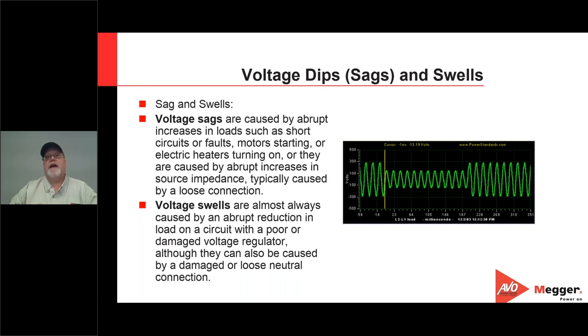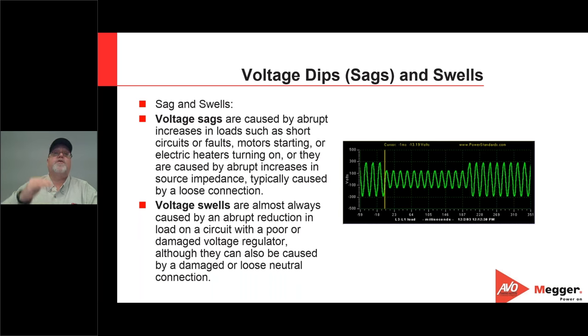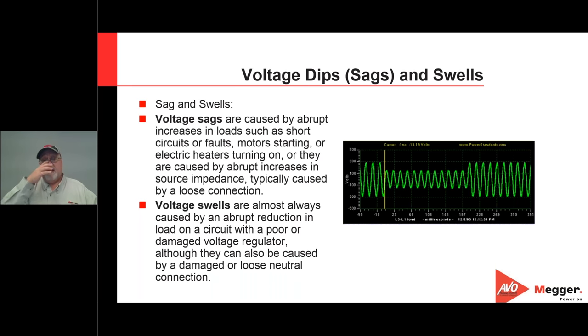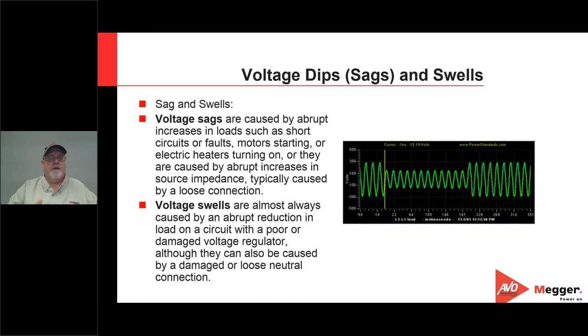Voltage swells are most commonly caused by large loads turning off. If you have a large motor with a lot of energy tied up in the magnetic field and you turn it off, that energy has to come down, and we're going to see a swell as the voltage rises. This can cause a breaker to trip. On a delta system, a phase-to-phase fault can cause the other phase to go high, producing an overvoltage or swell depending on how fast relay protection kicks in.